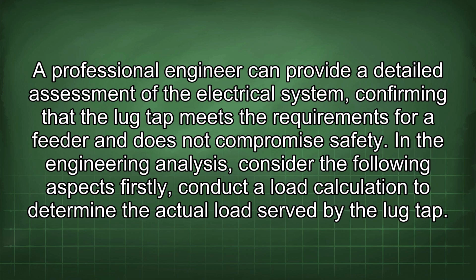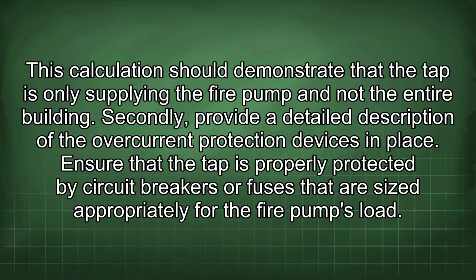Thirdly, if necessary, obtain an engineering analysis to further support your position. A professional engineer can provide a detailed assessment of the electrical system, confirming that the lug tap meets the requirements for a feeder and does not compromise safety. In the engineering analysis, consider the following aspects. Firstly, conduct a load calculation to determine the actual load served by the lug tap. This calculation should demonstrate that the tap is only supplying the fire pump and not the entire building.